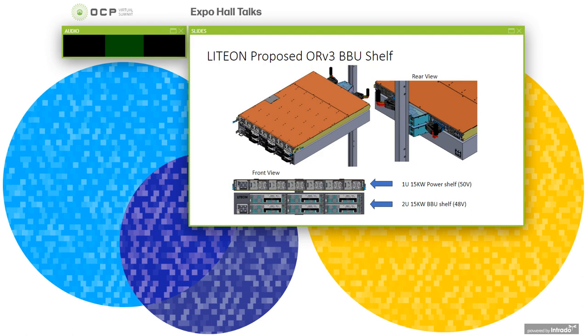One major consideration for ORV3 BBU is that it should be a standalone backup system, like an independent source. Physically, the BBU shelf doesn't even have to be next to the power shelf, unlike a previous design. This will enable the BBU shelf to be a truly modular building block in the rack, no matter if the rack requires N+1 or N+N. It could also support a different backup time versus power.